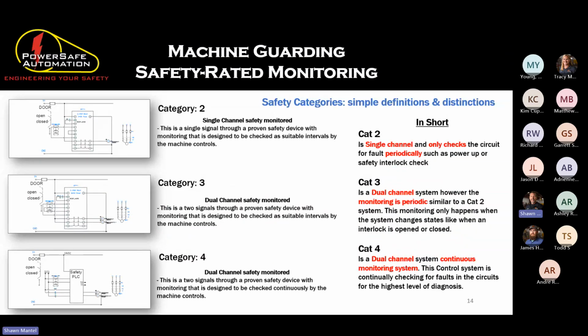I'm not going to go into all of these. You guys will get the video and the PowerPoint, but I'll run through this real quick. Basically, the way you monitor everything is going to determine what category level you are. You want to be a category 3 or category 4, where it's the dual channel safety monitoring. So the parallel lines, the simultaneous decision making, that's going to be category 3 and category 4. Category 2 we want to stay away from. That's going to be single channel. It's going to periodically check. It's only going to check one line. And there could be something wrong somewhere else on the machine that it just may not catch or catch in time. So we make sure that we are designing the circuits so that they're hitting the higher category levels.